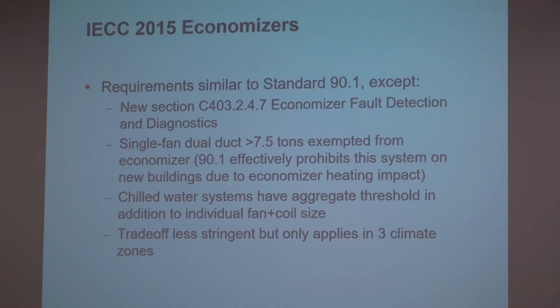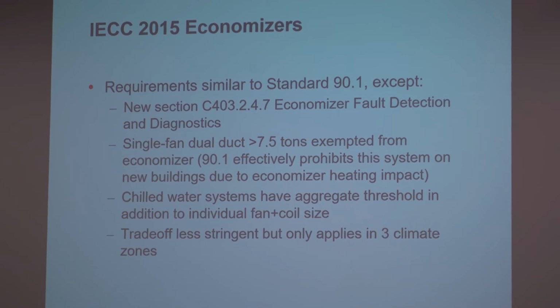All right. So the other thing that IECC did a little bit earlier than 90.1 is fault detection. When we have economizers that are working on our outdoor air intakes, we collectively as an industry surveyed a bunch of units, and we found economizers were either broken or disabled way too often, or they were economizing when they shouldn't be, or not economizing when they should have been. So fault detection came out of that significant emotional event about how useful our economizers really were. And so fault detection has been embedded into the controllers on unitary packaged equipment, primarily driven by California, but now it's countrywide through 90.1 and also through IECC.